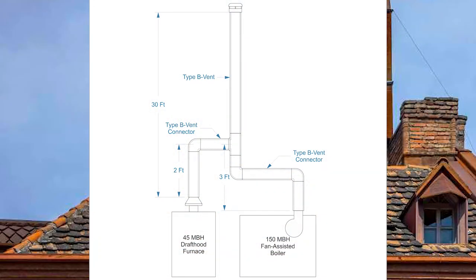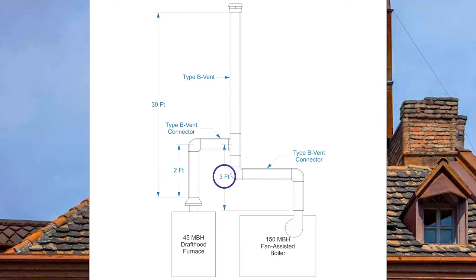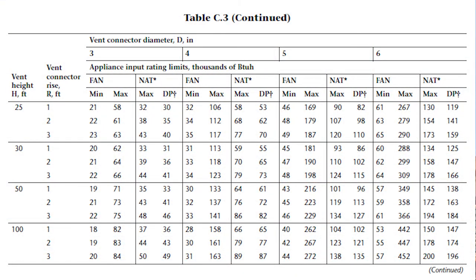For the last example I have a 30-foot common vent height with a 45,000 BTU draft hood equipped furnace and a 150,000 BTU fan assisted boiler. The furnace has a two-foot vent connector rise and the boiler has a three-foot vent connector rise. Both have double wall vent connectors, therefore we need to use table C3. Since the vent height is 30 feet, I need to turn to page 193, the second page of table C3.